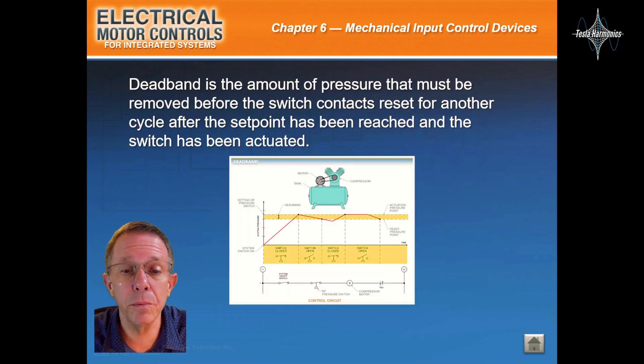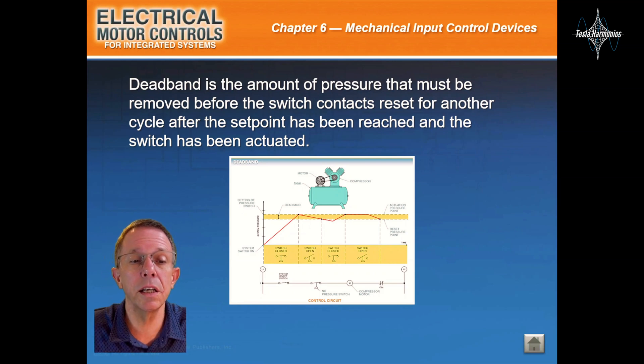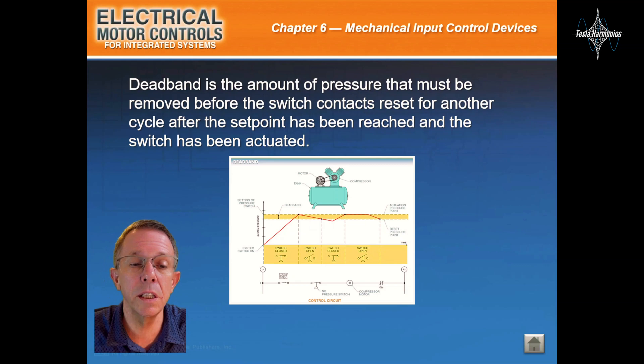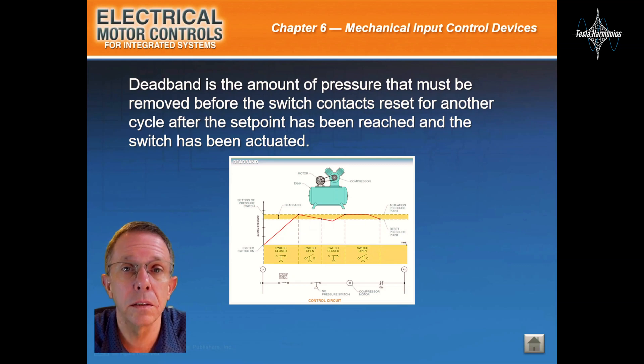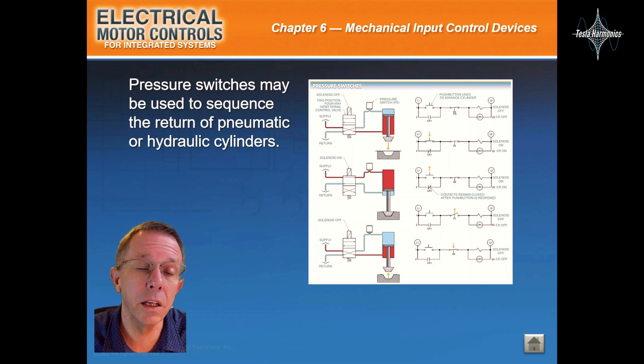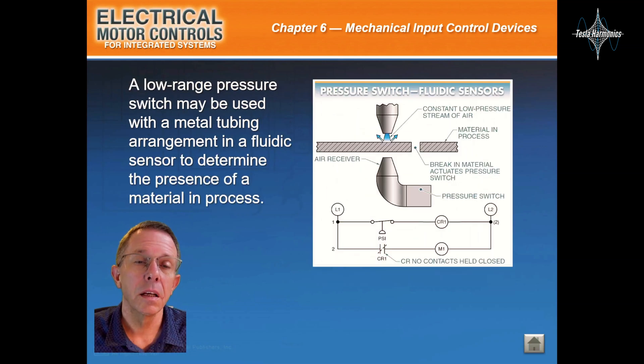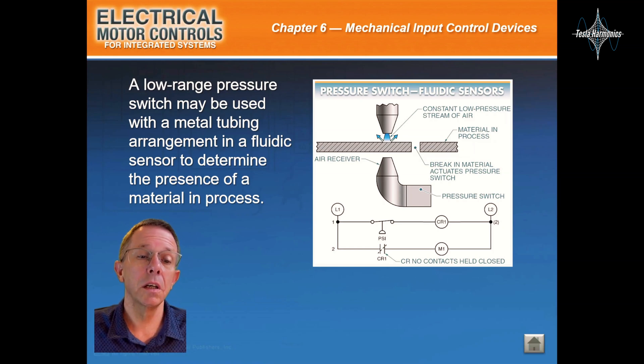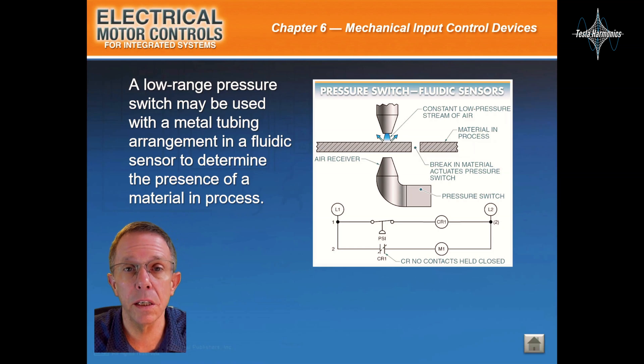Deadband is the amount of pressure that must be removed before the switch contacts reset after the set point has been reached and the switch has been actuated. Pressure switches may be used to sequence or return pneumatic or hydraulic cylinders. A low-range pressure switch may be used with a metal tubing arrangement and a fluidic sensor to determine the presence of a material in process.